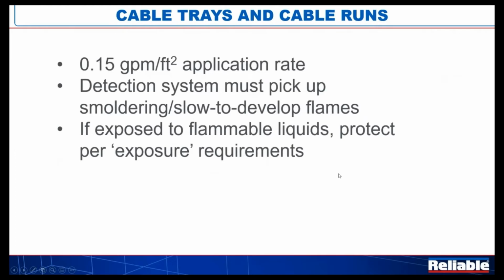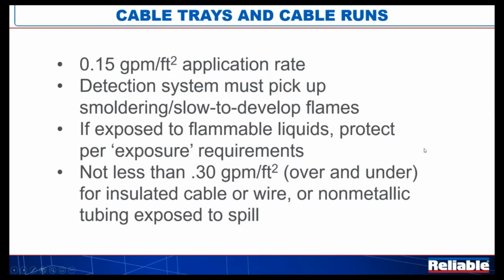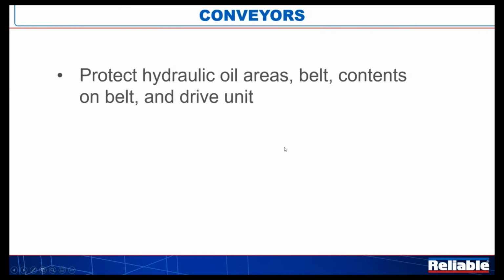If the cable tray is exposed to flammable liquids or molten materials above, we then go to the chapter or the section on exposure, and we're going to talk about that in a little bit. So just be aware if there's impingement from some fire hazard from above. In that case, we jump up the protection scheme to 0.30 GPM over and under. And again, that's for uninsulated, insulated cable where we have plastics and things like that, or non-metallic tubing exposed to a spill from above. So those are the basic rules for protecting a cable tray.